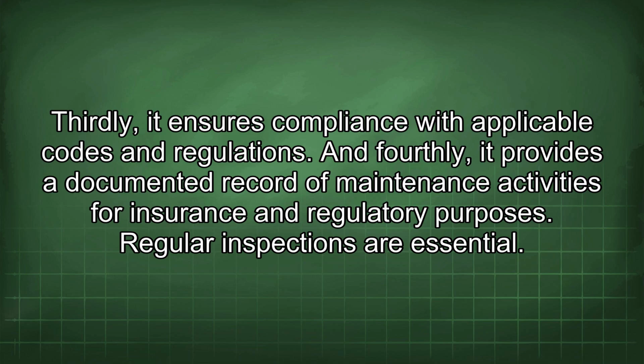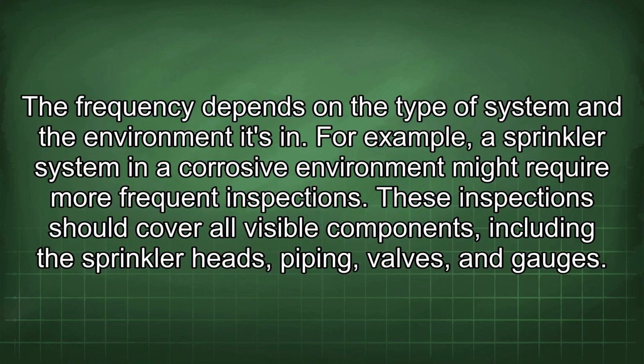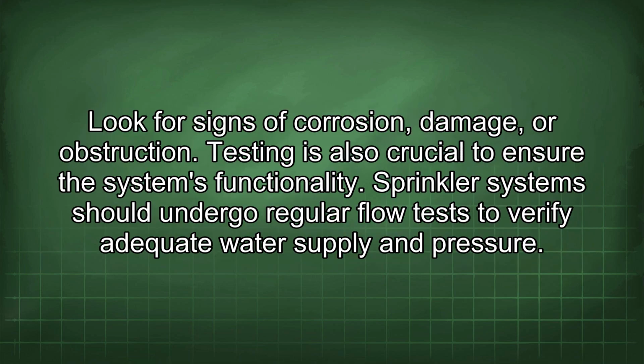Regular inspections are essential. The frequency depends on the type of system and the environment it's in. For example, a sprinkler system in a corrosive environment might require more frequent inspections. These inspections should cover all visible components, including the sprinkler heads, piping, valves, and gauges. Look for signs of corrosion, damage, or obstruction.